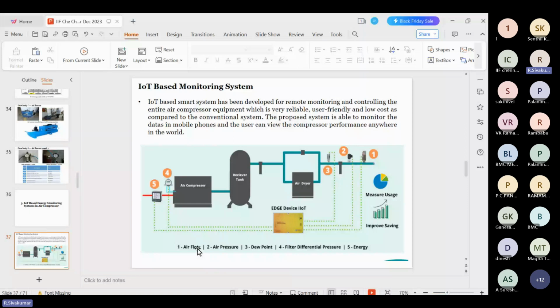This is an imported sensor, operated based on the temperature difference principle. Whatever the air pressure and the CFMs generated per air delivery, the airflow sensor captures the value and gives it to this IIoT device. The second one is to monitor the air pressure; there is a Danfoss process sensor. And the third one is the dew point measurement.